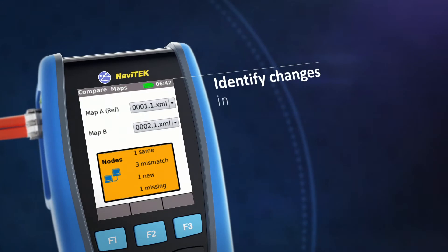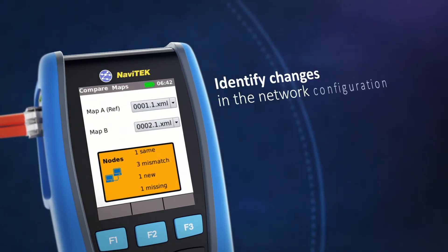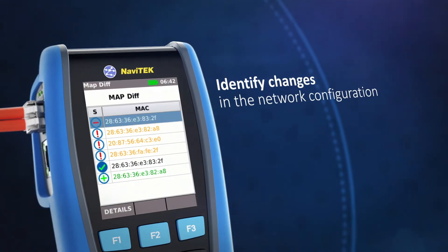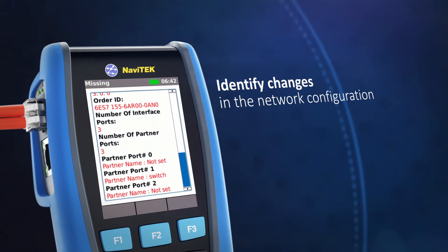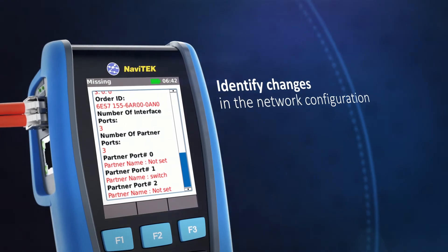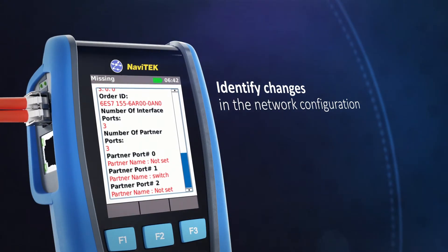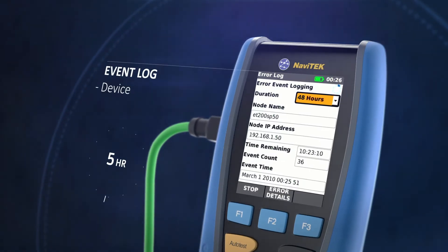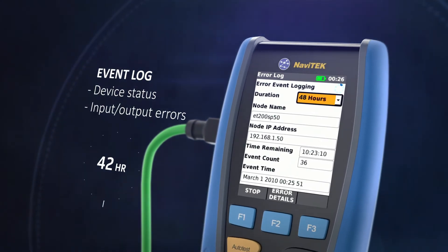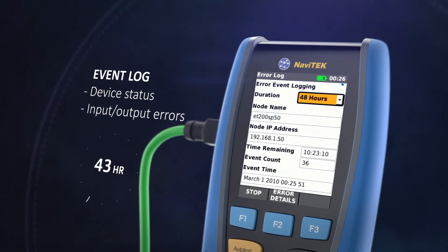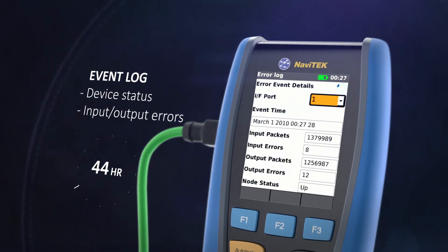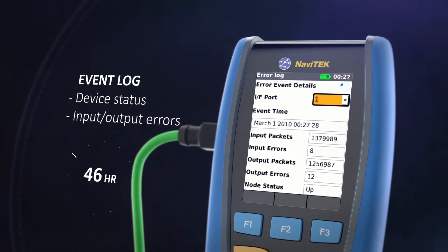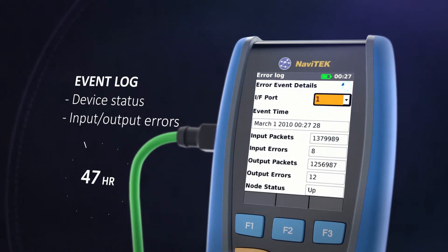The Navitech IE identifies changes in the network configuration by comparing against a previous test and indicates the source of a fault across network nodes. The event log feature helps to monitor intermittent issues by recording device status and input-output errors over a period of up to 48 hours.